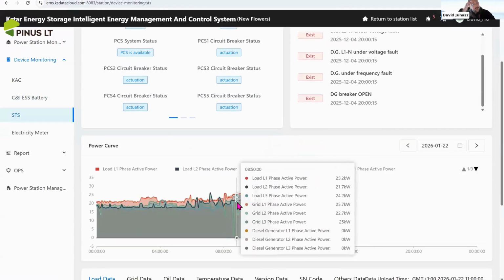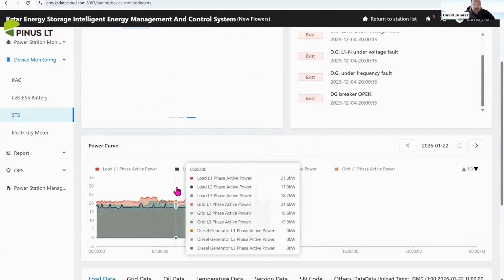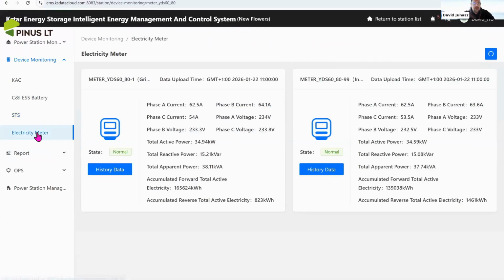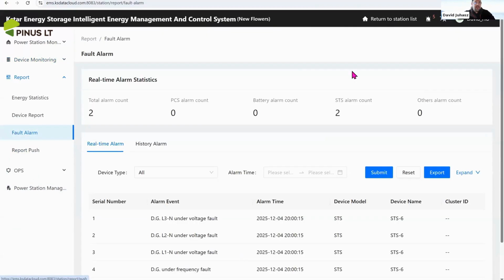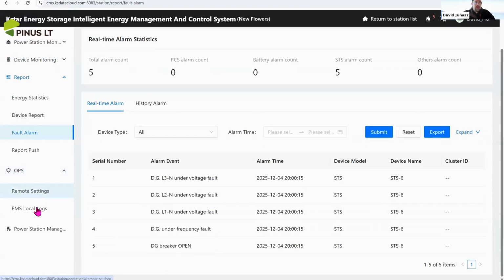We can see the STS device also on the AC side, what the powers are, and also the meter. We have 1 meter inside this STS and 1 meter at the grid connection point. We can make reports, energy statistics, and push reports to email addresses if there is any alarm occurring. And we have the remote troubleshooting.